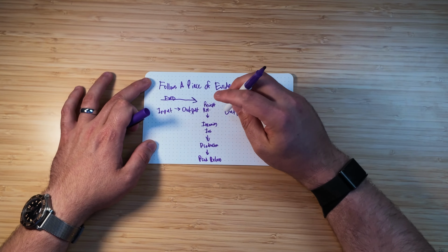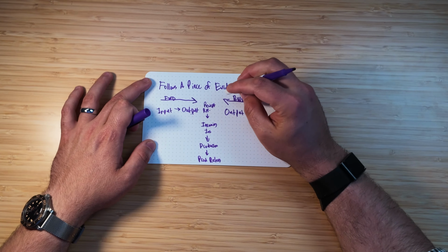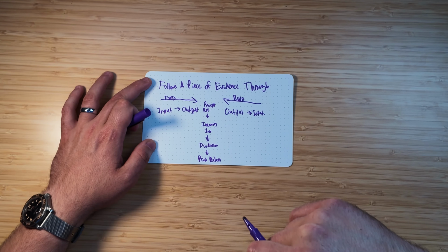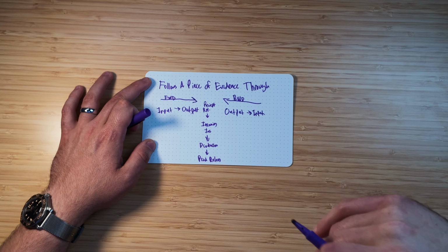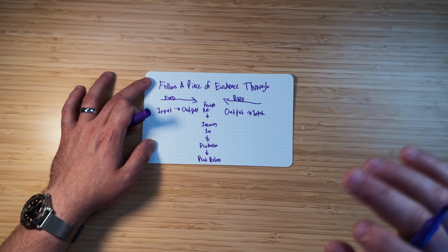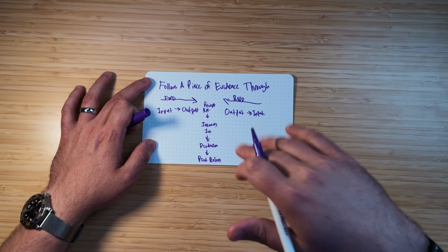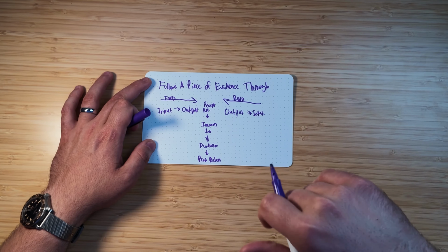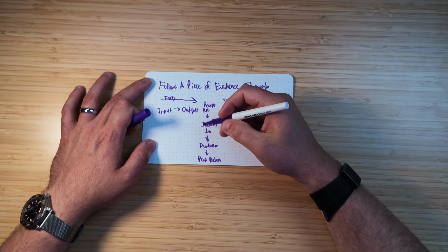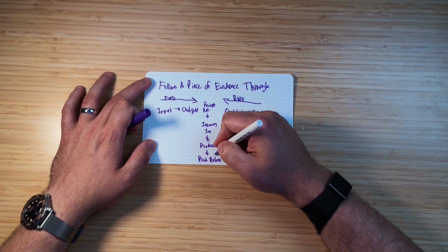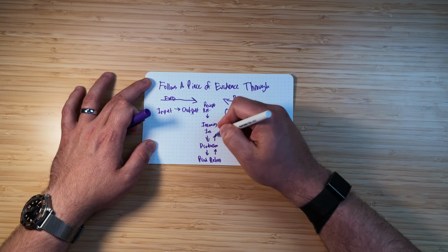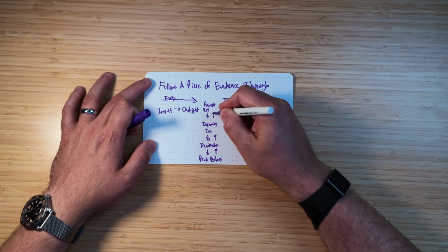And so you could say, show me a batch of incoming material, how it flowed in through incoming inspection, how you took it into production, how you did your material reconciliation and all of that, and what was left over. And then I want to see your release documentation, your batch records, etc. Or you could start at the batch record and then go backwards into production, backwards into incoming inspection, backwards into the receipt of the material.